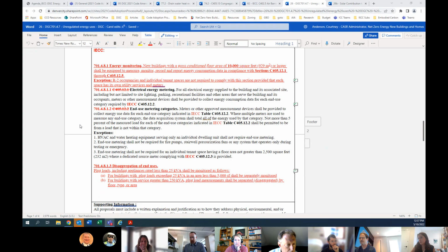The next one is that there's a disaggregation of end uses—plug loads, including appliances exceeding 25 kVA in an area less than 5,000 square feet, shall be separately monitored. And for buildings with service greater than 250 kilovolt amps, plug loads shall be disaggregated either by floor or by occupancy type or area.